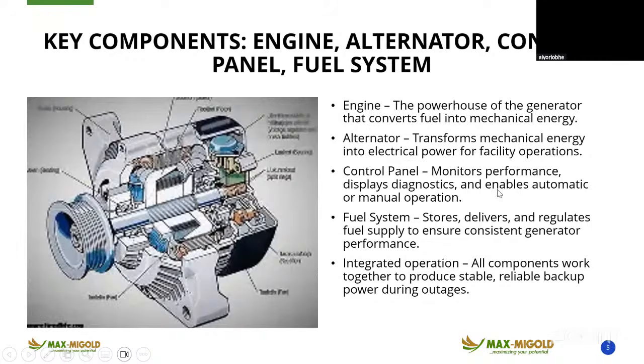We have the control panel. This is where monitoring is carried out: it monitors performance, displays diagnostics, and enables automatic or manual operation. This is the interface between the human and the generator, where every parameter is displayed so you can see how your generator is performing. If there's a fault, it's through the control panel you diagnose it and ensure faults are cleared and reported before running the generator again.